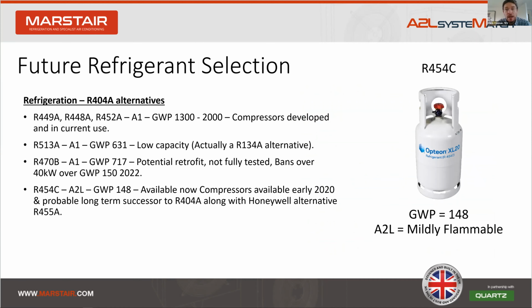So when it comes to refrigerant options, we chose R454C and its Honeywell alternative R455A. They're A2L class, so flammable, but less flammable than hydrocarbons, and the GWP is down at 148, so very much future-proof. There are also several compressors and components starting to become available and certified for use with these refrigerants. So for us, it was a sensible choice to take.